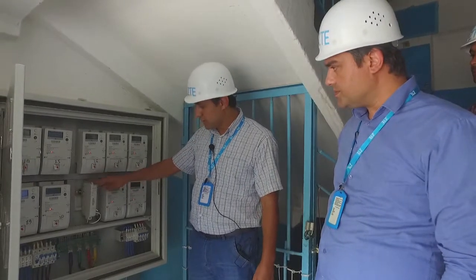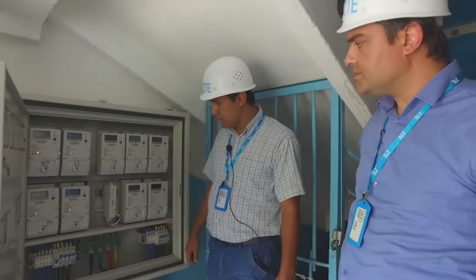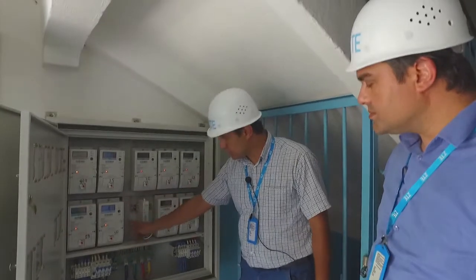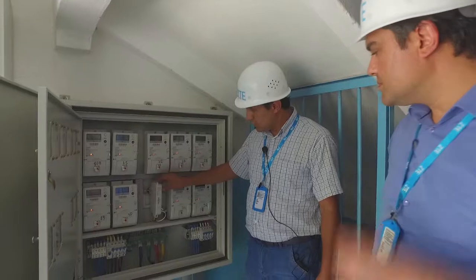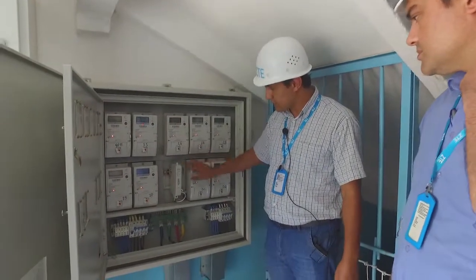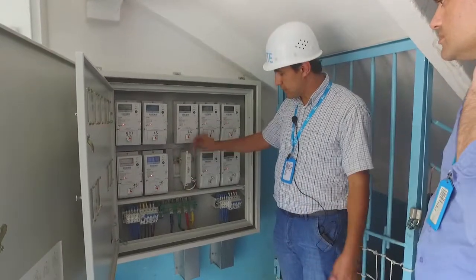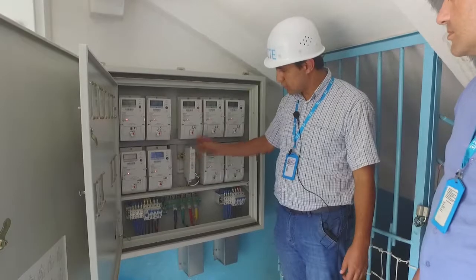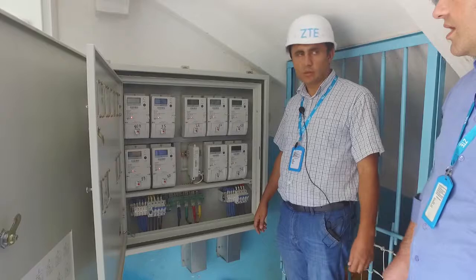So now we have PLC here. Every meter is connected to the PLC using the M-bus wire. The M-bus wire passes through this protective plastic. Then once the PLC collector gets the meters' information, such as reading data, or it can also pass signaling data, it can store it and send it to the TP data concentrator.